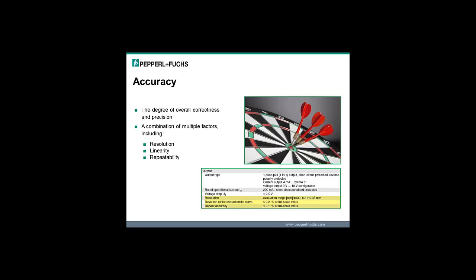And the accuracy is not a single factor. It's a combination of, typically with ultrasonics, 3 factors: the resolution, the linearity, and the repeatability. And you can see in this highlighted excerpt from a data sheet below, you can see the resolution, the deviation from the characteristic curve, which is an analog thing, and then the repeatability or the repeat accuracy. So all those 3 components go together to create the accuracy spec.